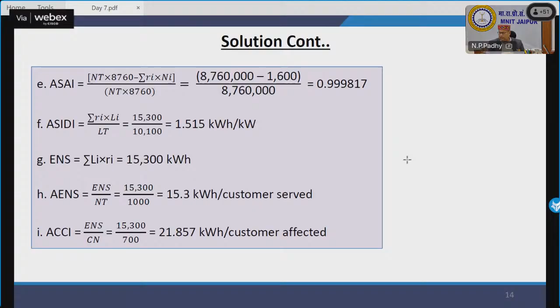Now moving to ASAI: NT times 8760 minus summation Ri Ni upon NT into 8760. That will be close to 0.999. You can also calculate ASIDI, which is 1.515 kilowatt hour per kilowatt. ENS, which is 15,300 kilowatt hour. AENS, which is 15.3 kilowatt hour per customer served. ACCI, which is ENS upon CN, which is 21.857 kilowatt hour per customer affected.